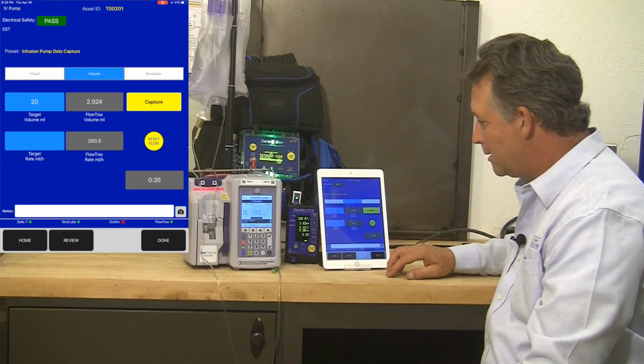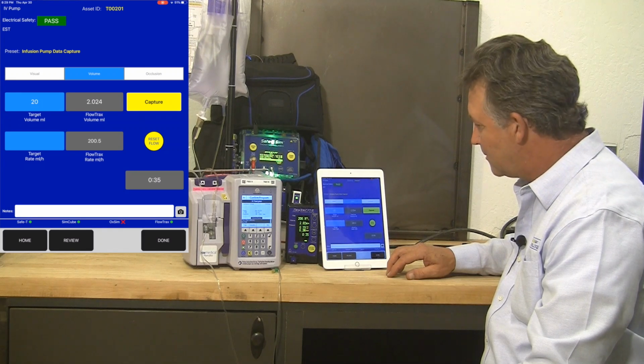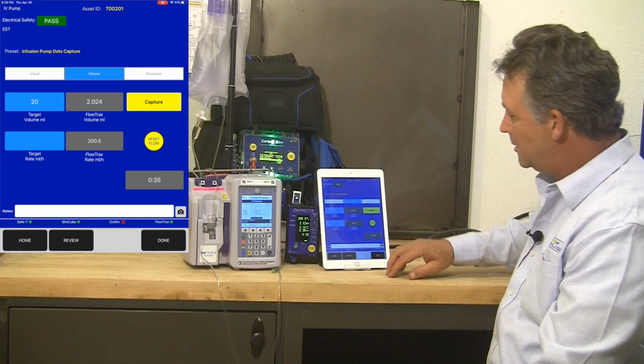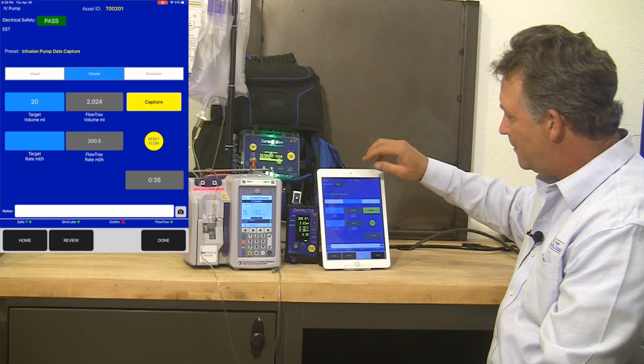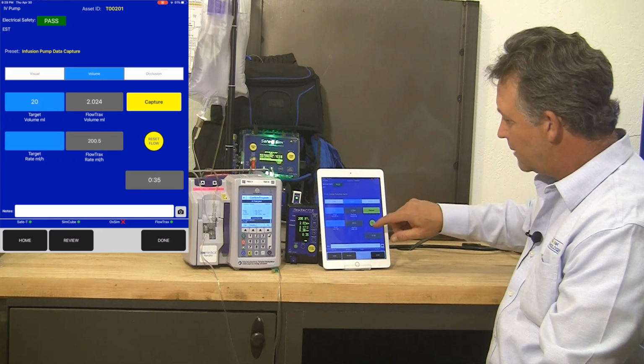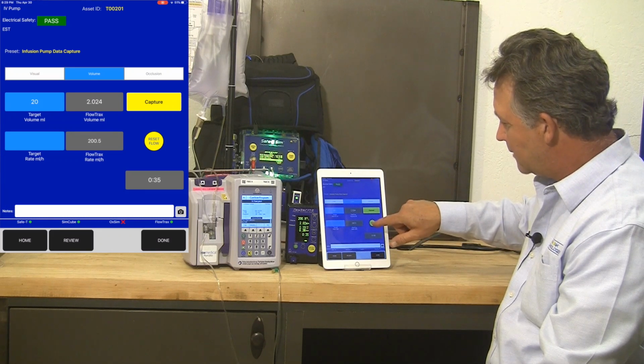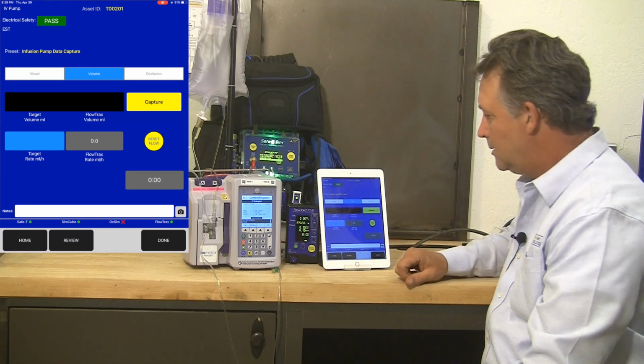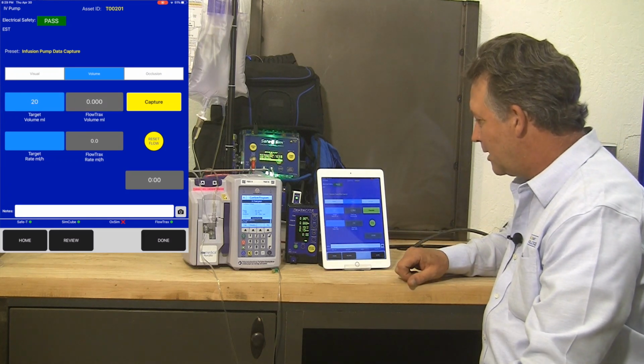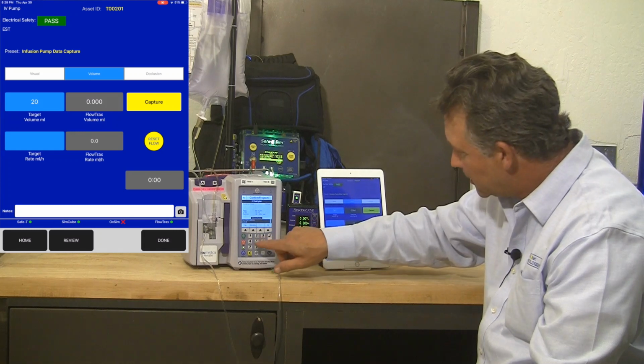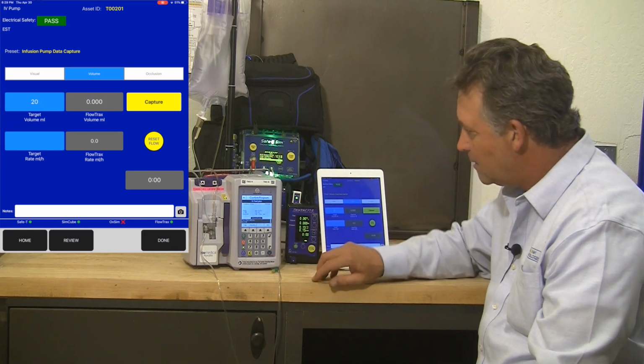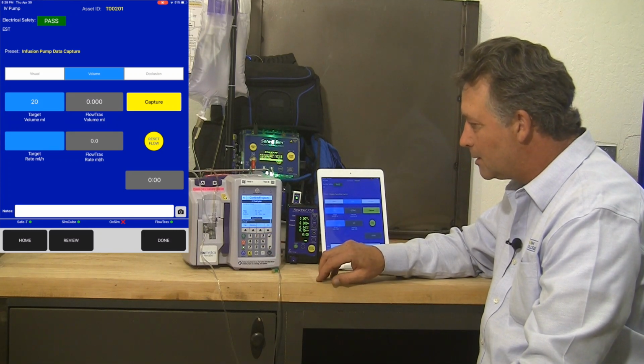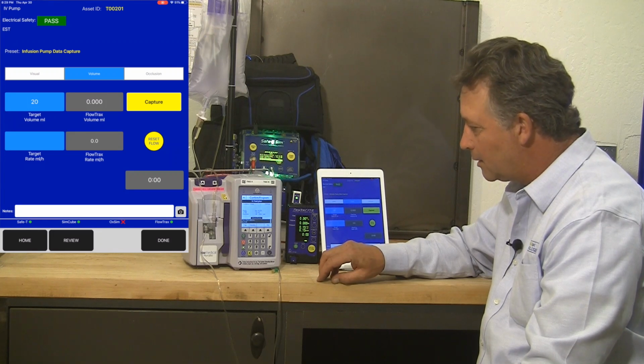Okay, now that we've completed our 2 occlusion tests at 6 and 10 psi, we're going to do a volume test using our iOS app. First thing we want to do before we start is do a reset flow. Again, the iPad is controlling the IV pump analyzer as well as capturing data. I've already programmed the IV pump for 200 milliliters per hour with a 10 milliliter volume for channel A.